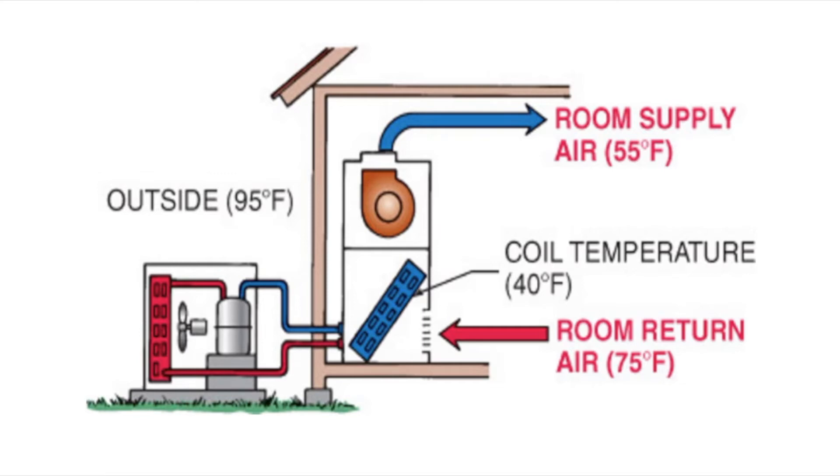We have the difference between 75 and 55, that's 20 degrees. Some people call that delta T temperature difference. So now we see that we have 20 degrees of temperature difference between the air coming in and the air going out. Ideally that's what you want. Ideally, that's the temperature difference you want between the air coming in and the air going out with a 40 degree coil.